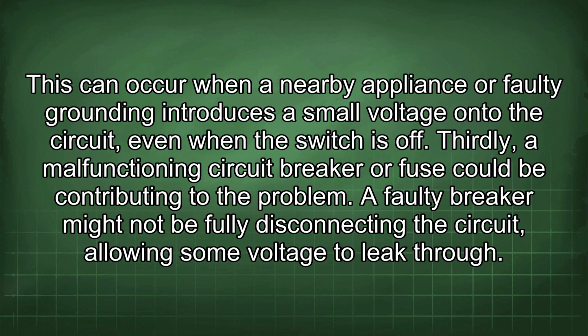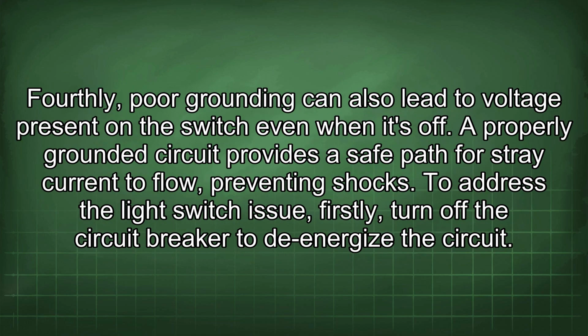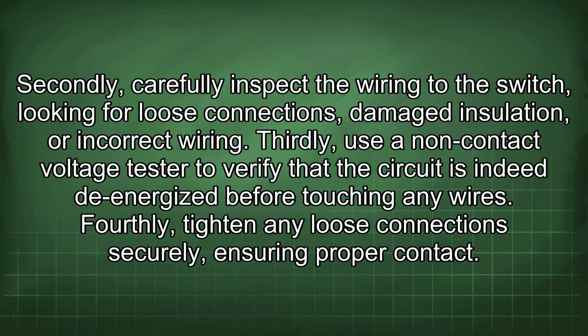A faulty breaker might not be fully disconnecting the circuit, allowing some voltage to leak through. Fourthly, poor grounding can also lead to voltage present on the switch even when it's off. A properly grounded circuit provides a safe path for stray current to flow, preventing shocks. To address the light switch issue, firstly, turn off the circuit breaker to de-energize the circuit. Secondly, carefully inspect the wiring to the switch, looking for loose connections, damaged insulation, or incorrect wiring.